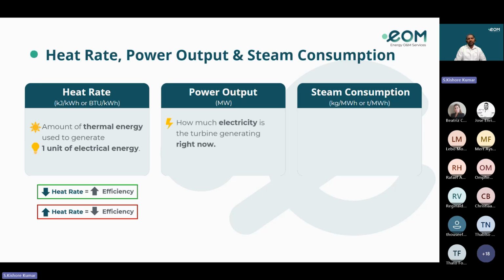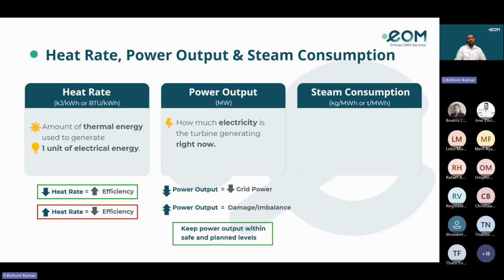Coming to the power output: how much electricity is the turbine generating right now? It is measured in megawatts, and real-time monitoring helps operators know if the turbine is performing as expected. So why does it matter? The turbine needs to match what the grid power network needs. Too low, and the grid might not have enough power; if it is too high, that can damage the system or cause an imbalance. So our goal is to keep power output within safe and planned levels.